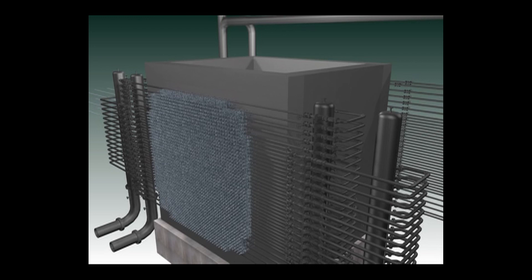Nozzles are then attached to the outside shield faces and the process tubes are sealed to the inner diameter of the nozzles. A small tube called a pigtail connects the cross header to each nozzle. The water flow for each process tube can now flow from the riser to cross header to nozzle and into the process tube.